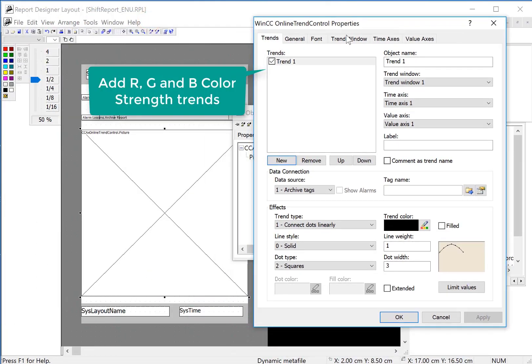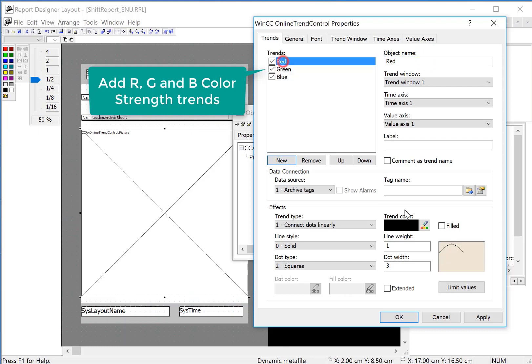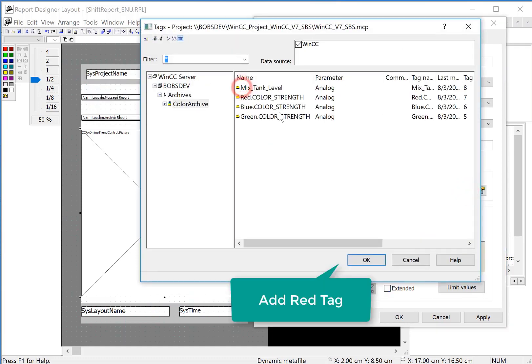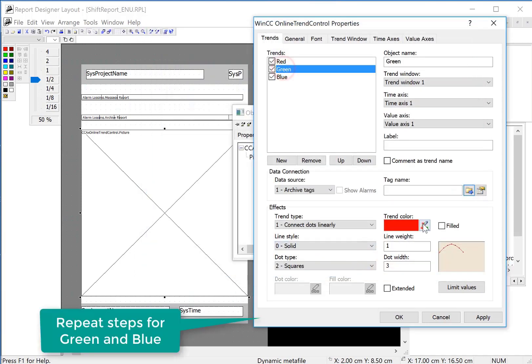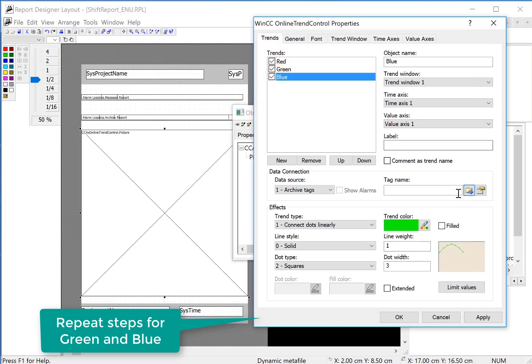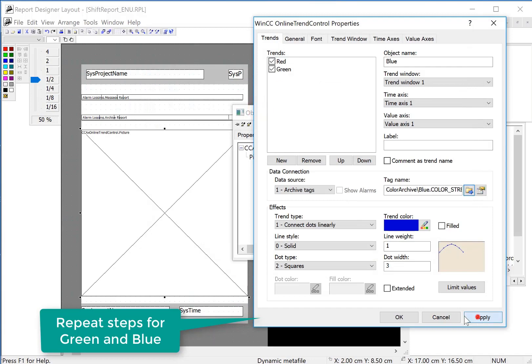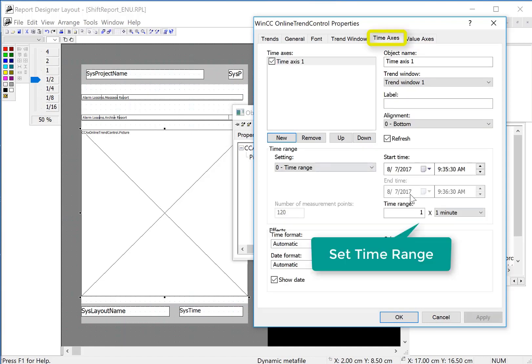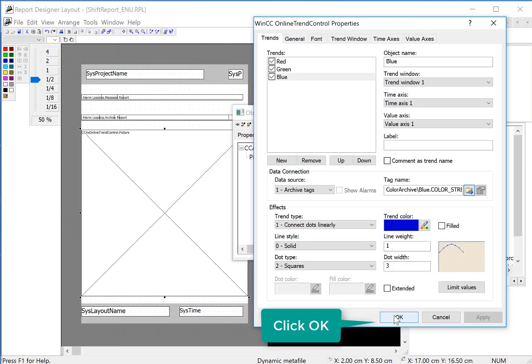On the properties you can see this is just like a regular trend control. So we will configure our red, green, and blue color strengths. For red I'll choose a red color and link it to our red color strength archive. Then for green we'll do the same thing — choose a tag name here. We'll hit apply, then look at our value axes and set this 0 to 100. Then on our time axes — this is how much time the window represents — we'll set this for 20 minutes. Then we'll click OK.